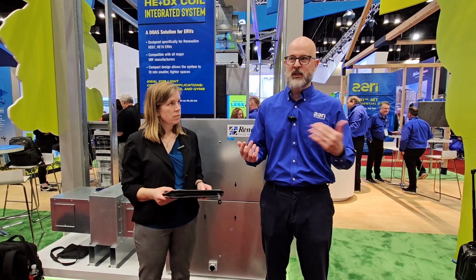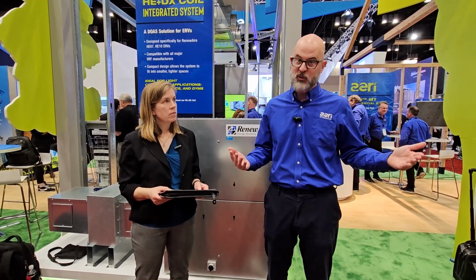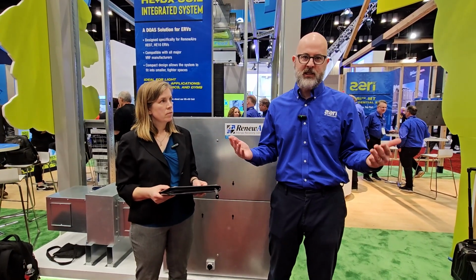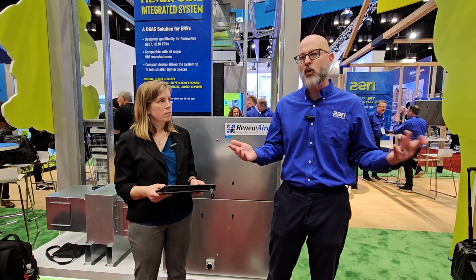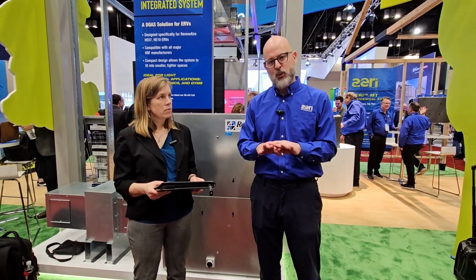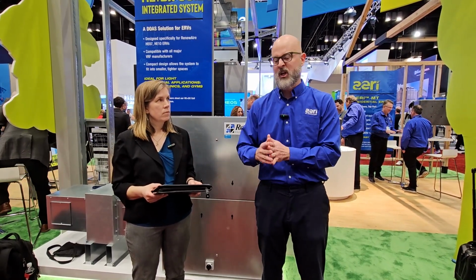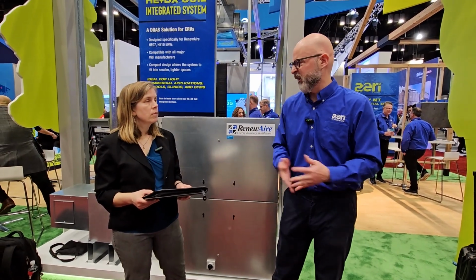Ultimately, there are extreme cases though, and so you're going to need some kind of post-conditioning. But imagine if you didn't have that plate heat exchanger, then you would just be covering the entire load with whatever cooling device you have, such as a DX coil, chilled water, or whatever. You would do the entire load. So at least with our plate heat exchanger, you're rejecting some of it initially and then cooling the final bit afterwards, or rejecting the moisture afterwards. So that's the idea, basically.